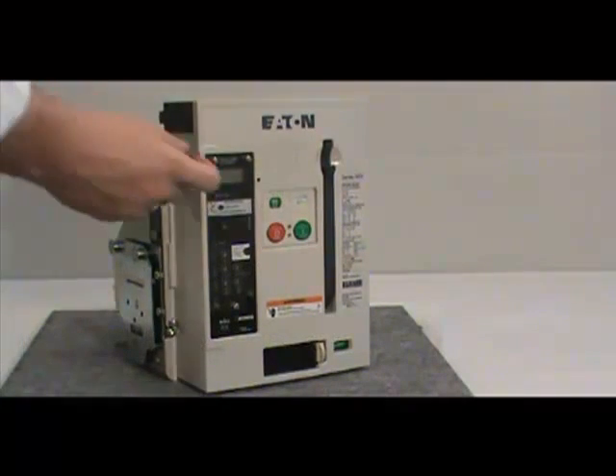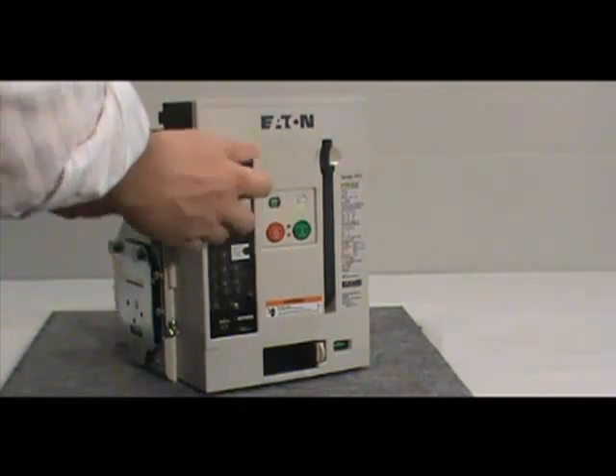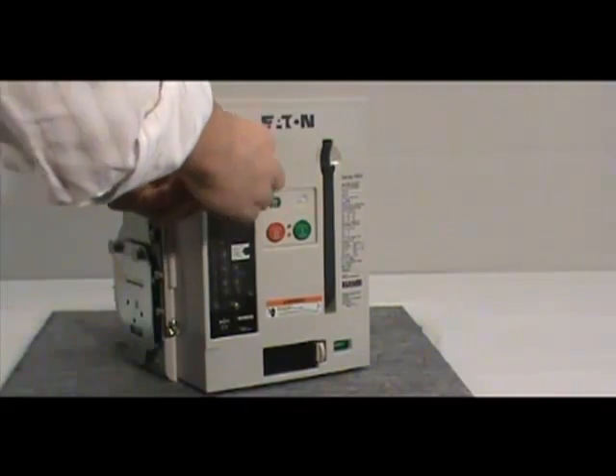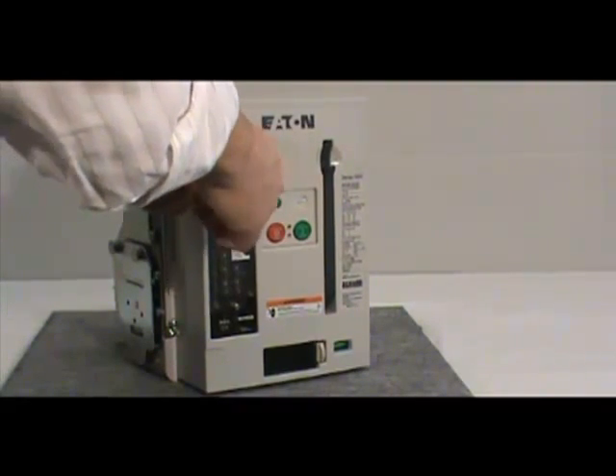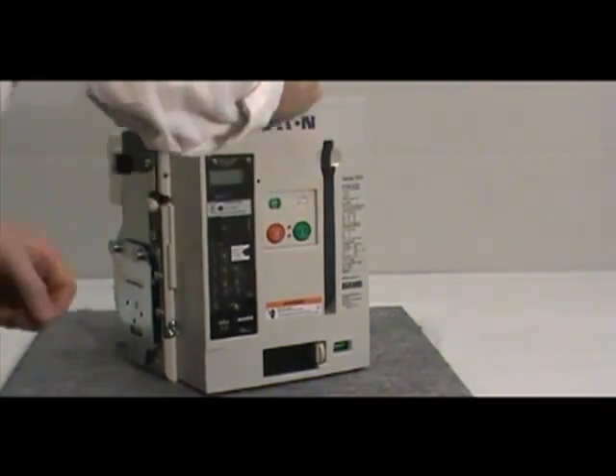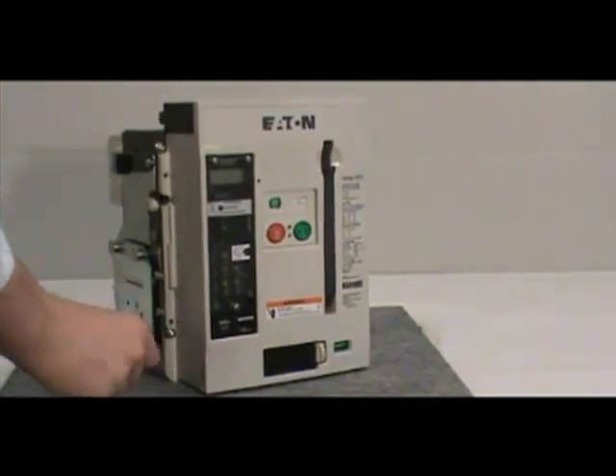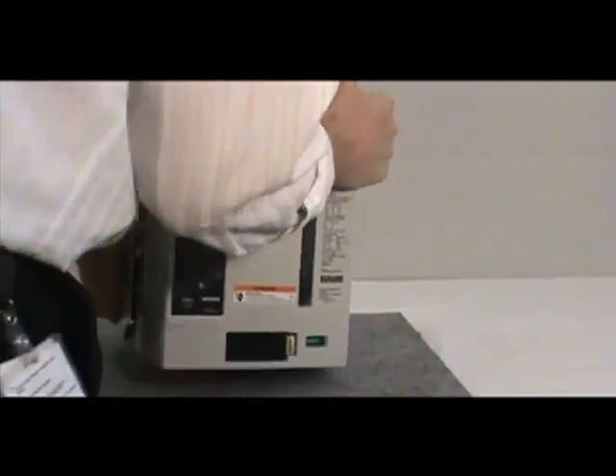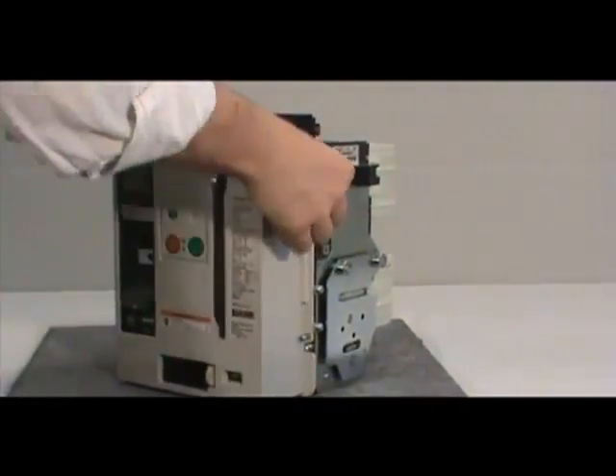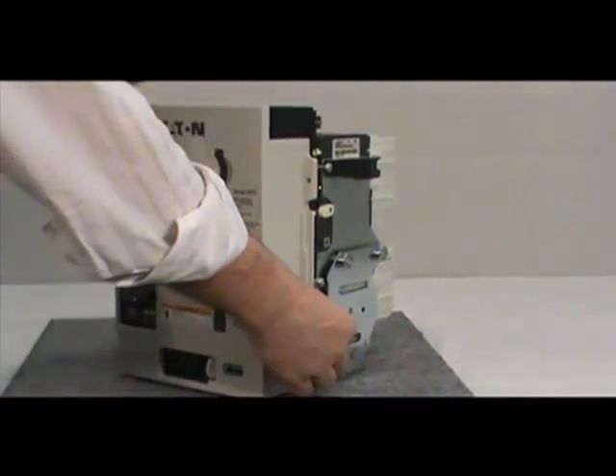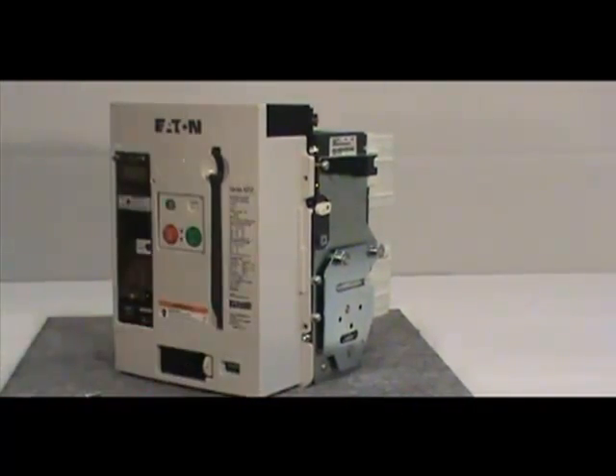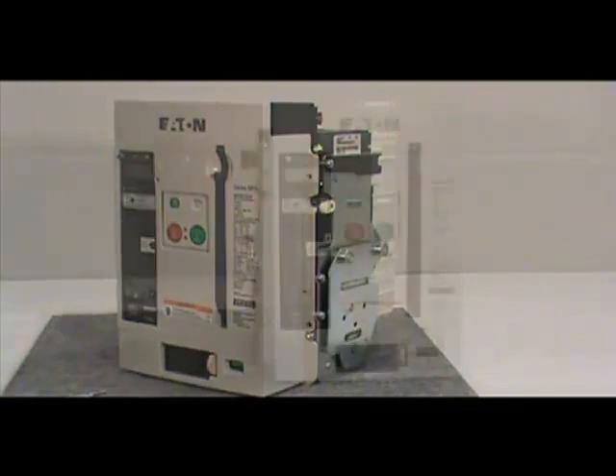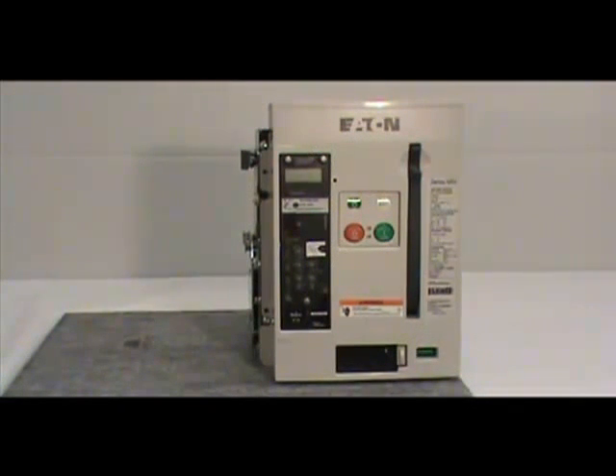Before proceeding with the installation, you must remove the front cover of the circuit breaker. If you have a three pole breaker, you must remove the four non-captive screws with the number two phillips head screwdriver. If you have a four pole breaker, there are six screws to be removed. Make sure you save the screws for reinstallation. Once you've done this, pull down on the charging handle for easy removal of the cover from the breaker.